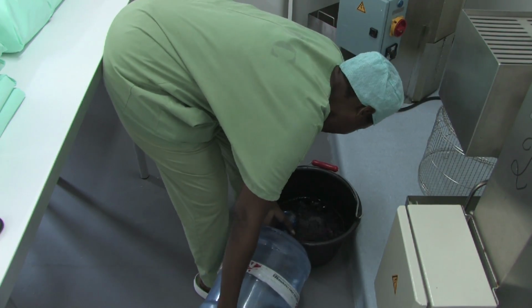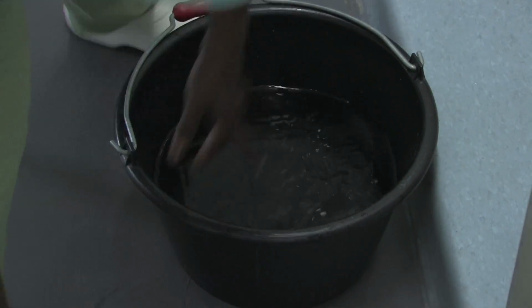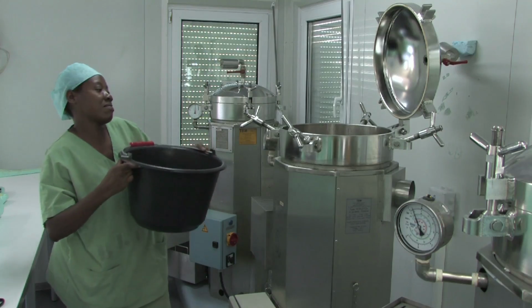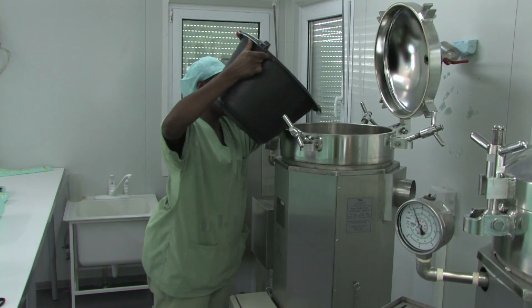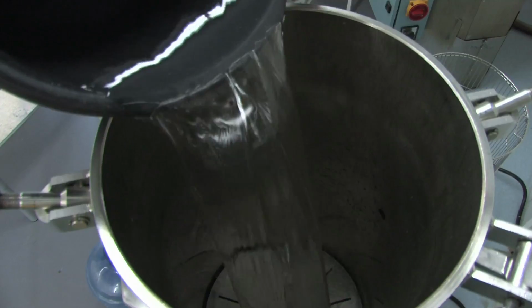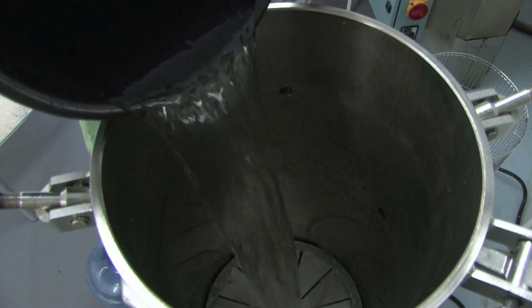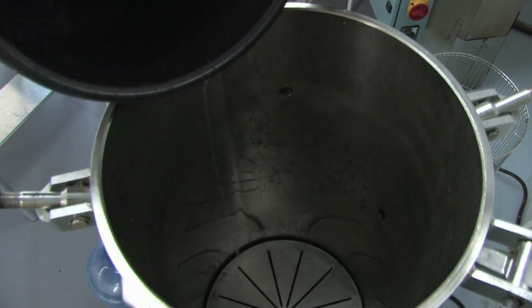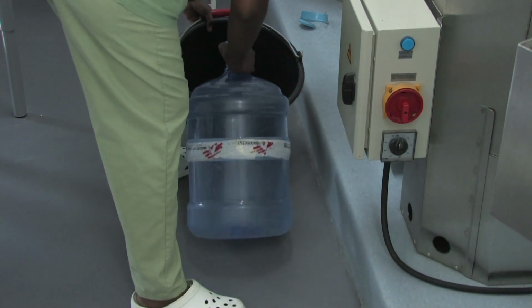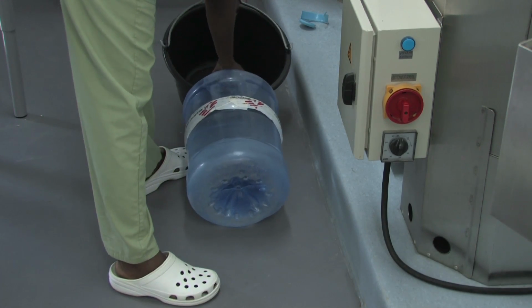2. Pour the amount of water needed for electrical operation in the autoclave chamber, that is, 16 litres. If the autoclave must operate using a different energy source, such as gas, add only 8 litres, because the electrical element need not be covered by water.